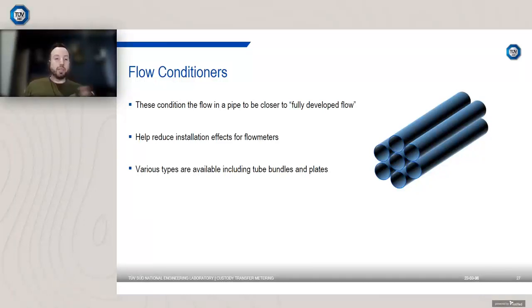I'm just going to finish the metering section on flow conditioners. So we've talked about various technologies that require a nice fully developed flow. Now, the best way to achieve that is to provide long straight lengths of pipe. This allows any effects like swirl to dissipate before it gets to the flow measurement device. Now, what if you don't have the luxury of that, or if you've got limited space? Well, you can shortcut your way to fully developed flow using a flow conditioner.